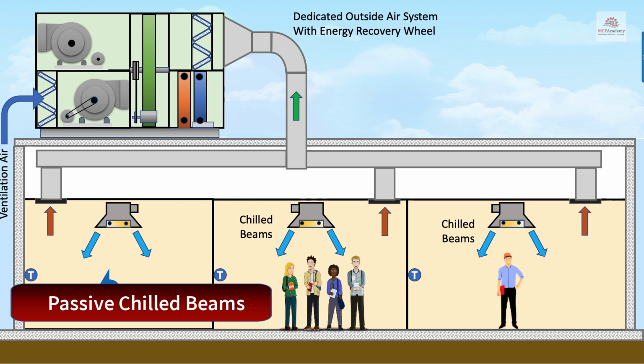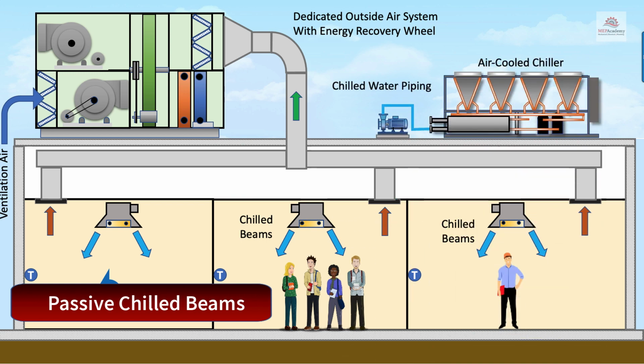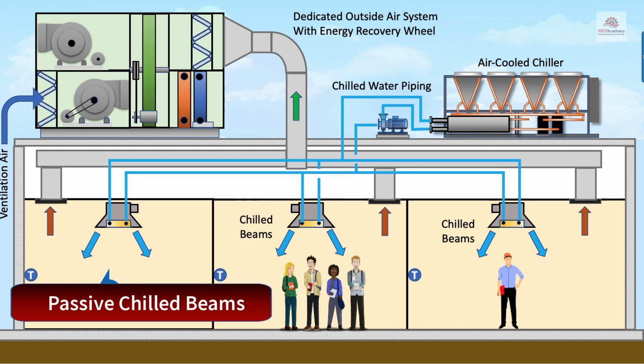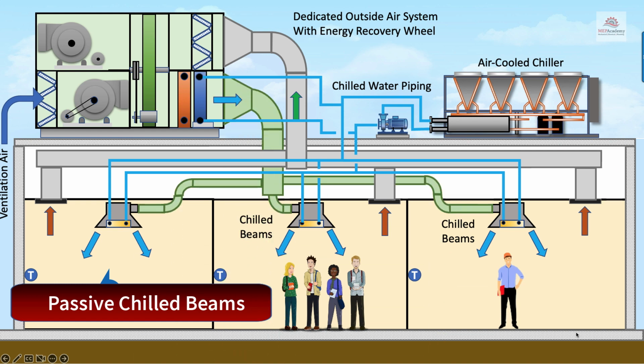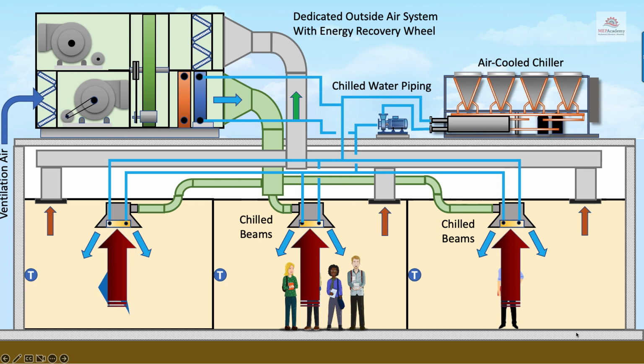Using chilled beams will require the installation of a chiller, in this case an air-cooled chiller mounted on the roof and piped to the chilled beams and the DOAS unit. The ventilation air from the DOAS unit will pass through the chilled beam, inducing room air up into the center and through the cooling coil and back into the room. It's important to keep the chilled water to these chilled beams above the dew point temperature to avoid condensation, as there are no drains used on these units.